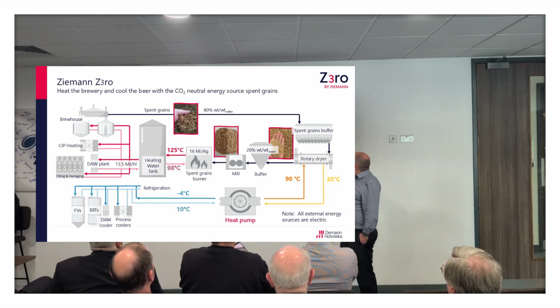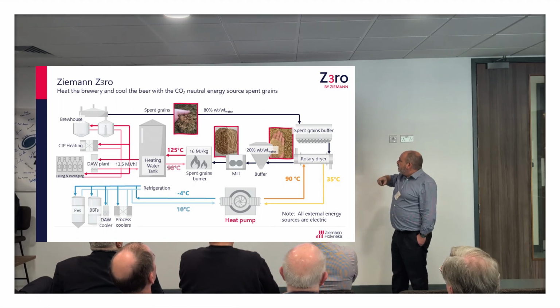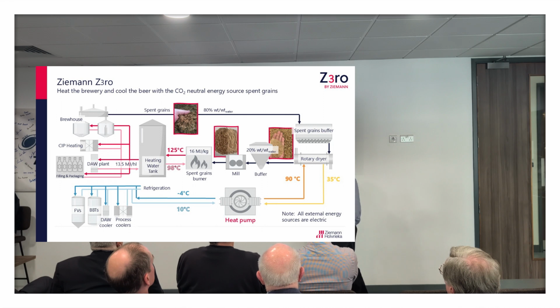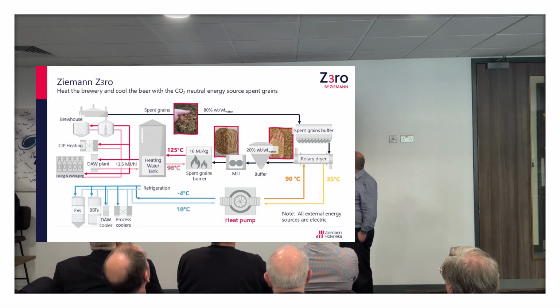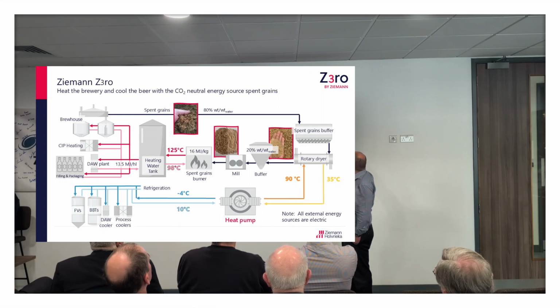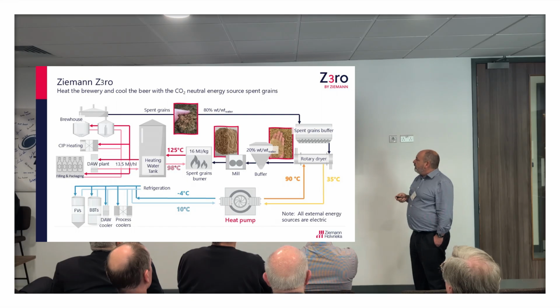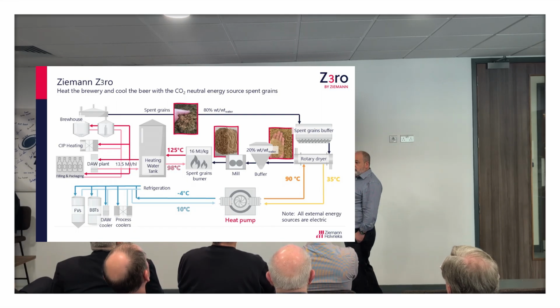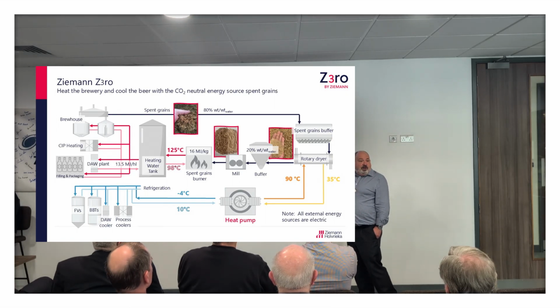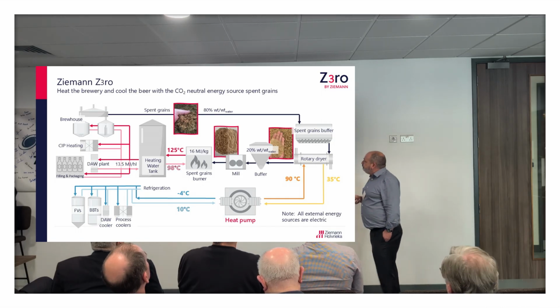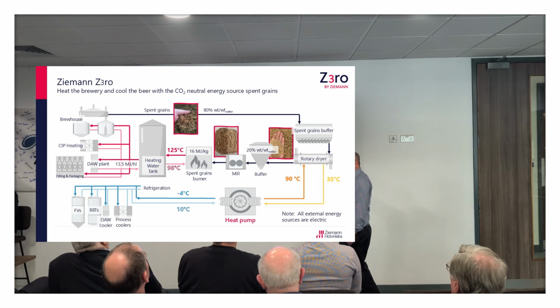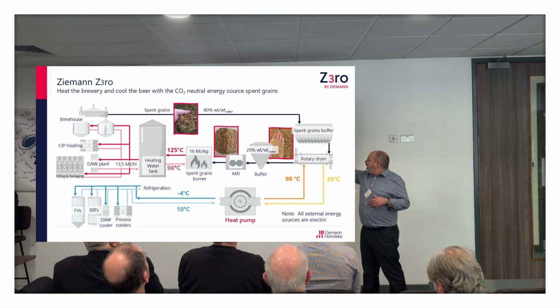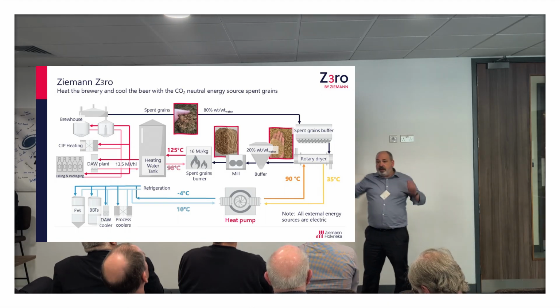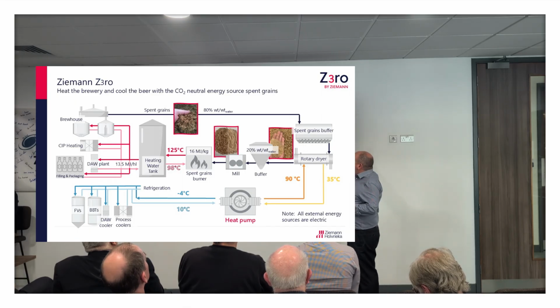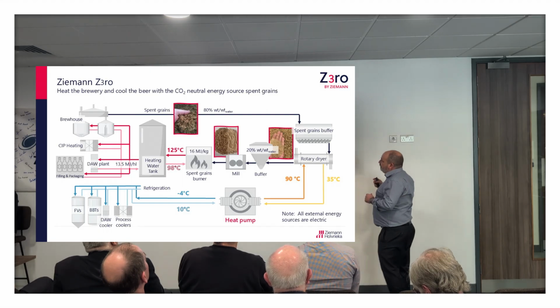And clearly we need to provide energy for the dryer, and here we're using a heat pump. That heat pump is using for its heat source the refrigeration energy that we need to take out of the refrigerant, and then we're boosting that through the heat pump to 90 degrees to power the dryer. And a heat pump in that configuration will have a coefficient of performance of between 2 and 3, probably around 2.5, perhaps a bit more. That type of heat pump, typically double cascaded mechanical refrigerant-based systems, they're available. You can buy those from suppliers. None of this is novel technology. It's just combined together in a different way.